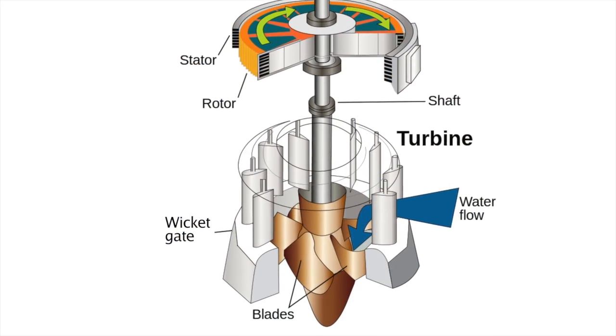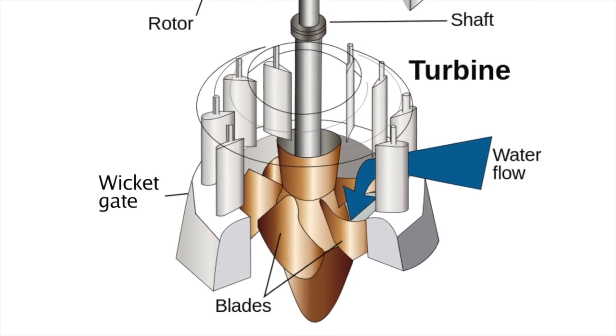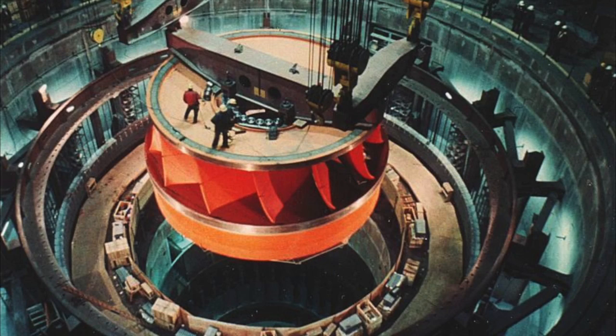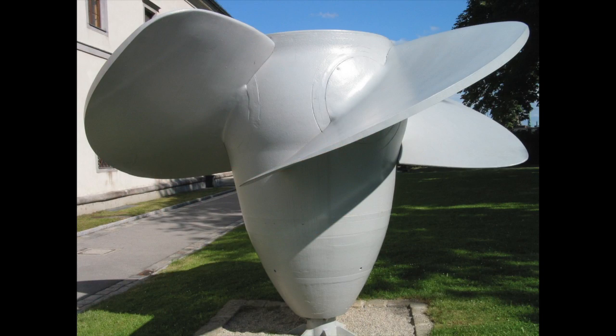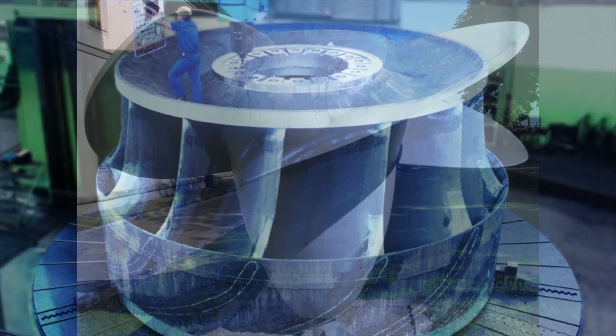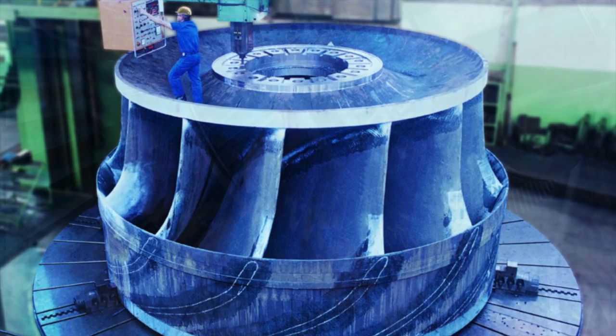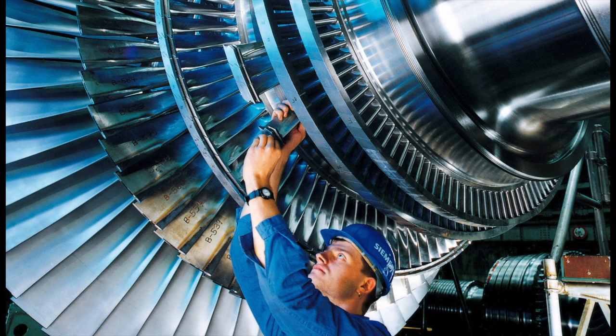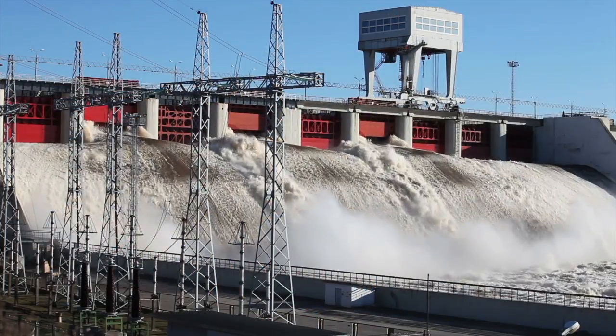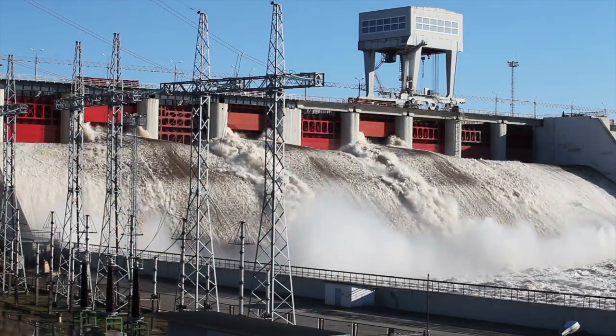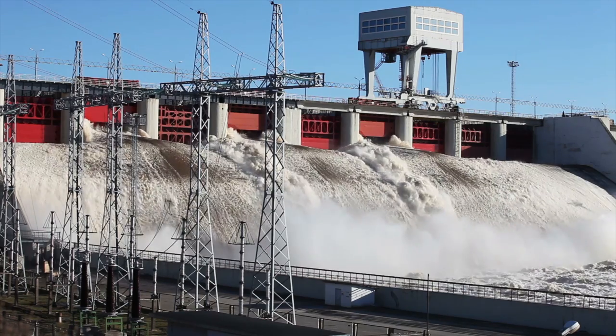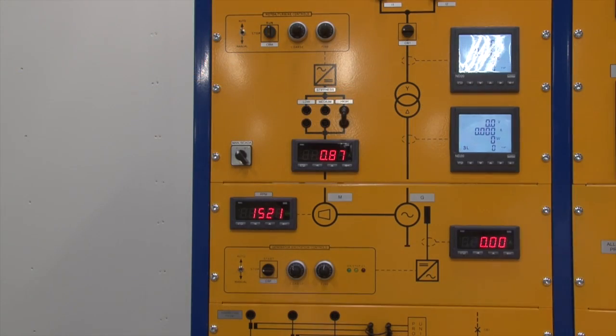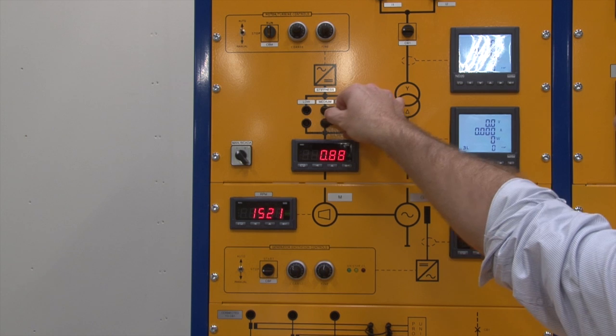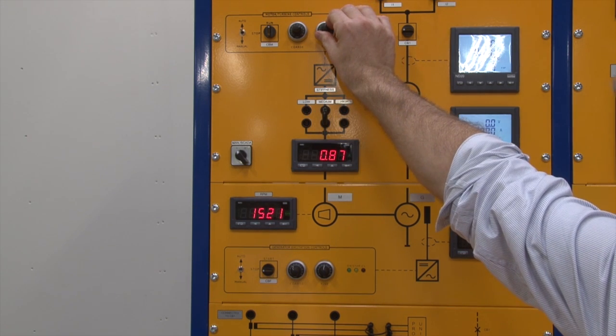To create power, we must first have a prime mover, or turbine. The different types of prime mover used in different power stations exhibit certain characteristics, such as reaction times and load sag, due to governing techniques and physical system properties. One example of contrasting system properties is the difference between trying to stop the inertia of thousands of tons of water flowing through a hydroelectric power station compared to stopping or redirecting the inlet of steam in other types of power stations. On the PST 2210, turbine characteristics can be set quickly and frequency controlled and monitored efficiently.